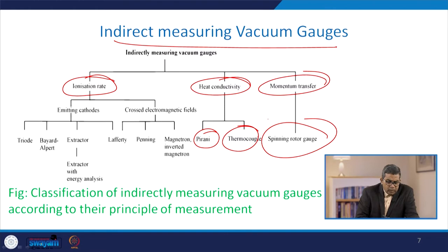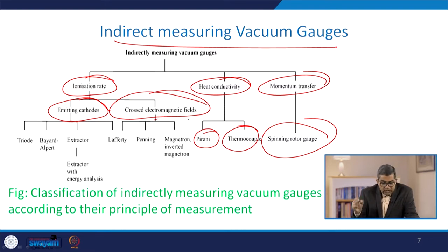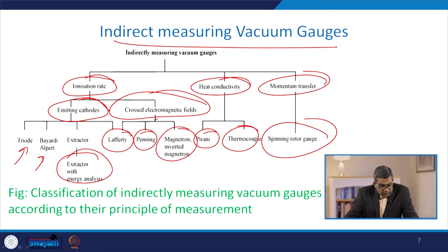Regarding ionization rate, there are two sub-categories: emitting cathodes and gauges based on crossed electromagnetic fields. The crossed magnetic-electric field type is further subdivided into three: Lafferty, Penning, and magnetron/inverted magnetron. The emitting cathode type is subdivided into triode, Bayard-Alpert, and extractor, with the extractor also referred to as the extractor with energy analysis.